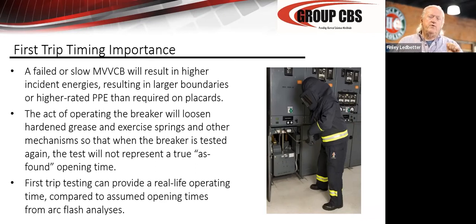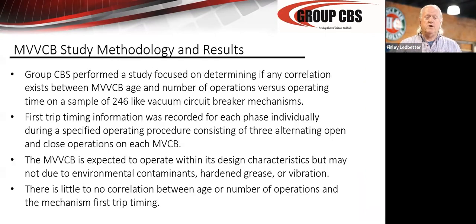Once you open the breaker the first time, you lose that data because you've exercised the grease and it's going to operate a little quicker next time. So you really need to try to come up with a way to get first trip timing to validate your maintenance program. When I say that, what I'm talking about is, let's say you're cleaning and lubricating the breakers on a 3-year period, and these times continue to be consistent, maybe you can go to 4, maybe you can go to 5. If you're maintaining it on a 5-year cycle and your times are slow, then you need to cut it back.